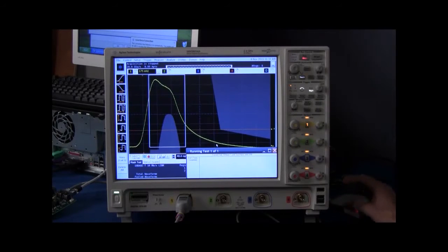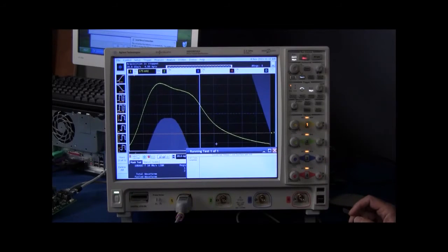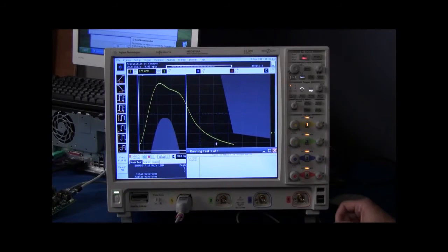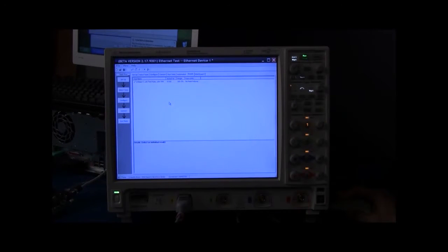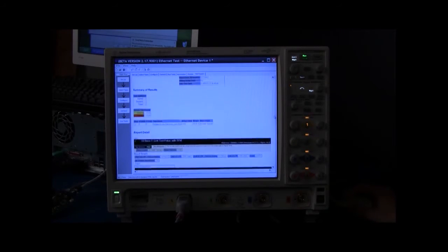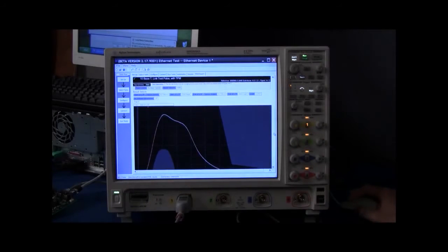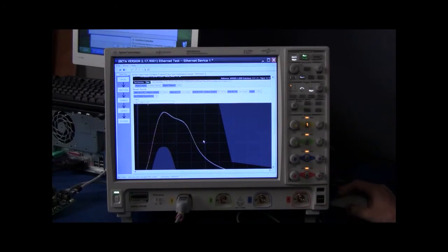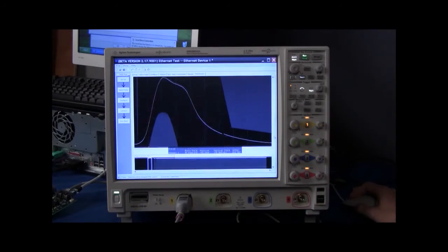As this runs, you can see it running through the compliance application tests with all the templates for this particular test. Once we've ran through our tests, you'll notice that in the results tab here, we can see the test has passed. We can actually see the HTML report. It gives us a nice status of our pass status. And it also shows us the details of the report as far as our mask tests and pictures relevant to those tests.